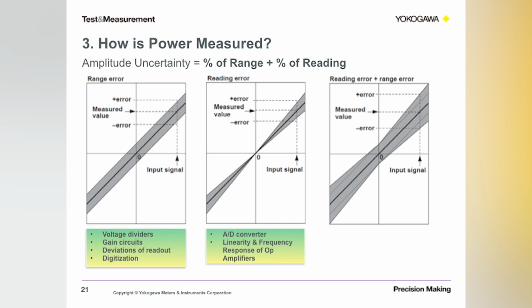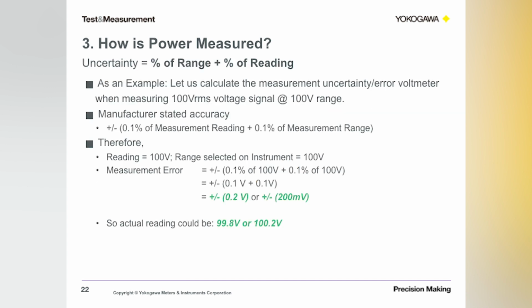All right, let's take an example of how to calculate uncertainty. Take the measurement uncertainty of the voltmeter we selected in our first example, and see what the uncertainties are if you're measuring a 100 volt RMS signal at the 100 volt range. Say the accuracy provided by the manufacturer is 0.1% of range plus 0.1% of reading. If you work through the math, as I've shown here, you will notice that there is an uncertainty of plus or minus 200 millivolts, as you calculate 0.1% of 100 volts plus 0.1% of reading, and that will give you 0.1 plus 0.1, which is 0.2 volts, right?